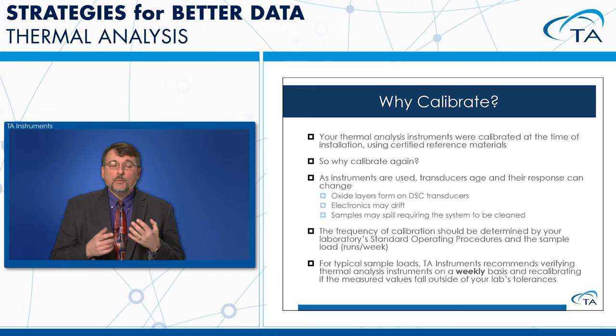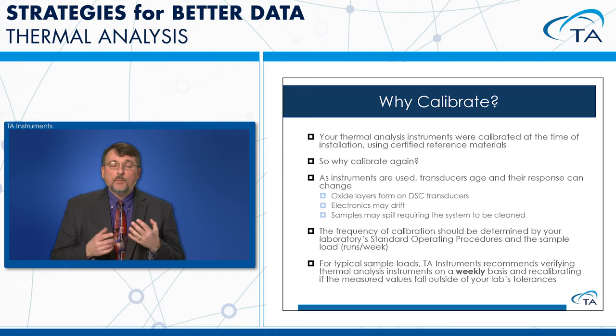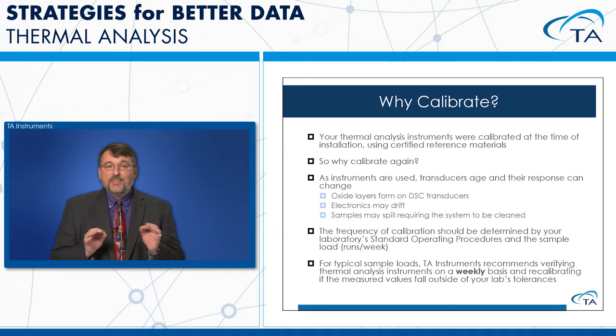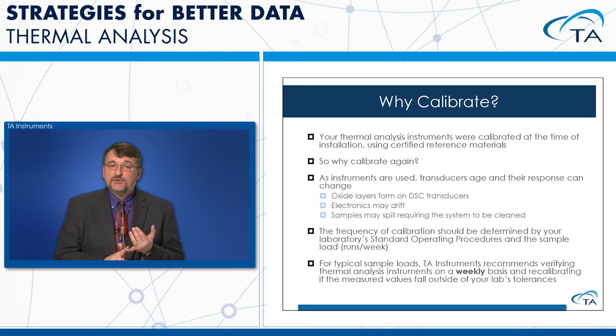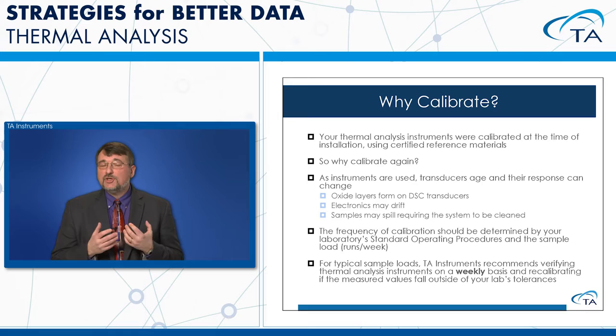When we talk about calibration, the first question might be: why do you calibrate? When you bought an instrument from TA Instruments, it was installed, set up, and calibrated by TA's service specialist using ASTM standards for best performance. Over time, sensors can age, electronics can drift, oxide layers can form in the DSC sensor, and samples could get spilled into the cell — all reasons you might need to recalibrate.